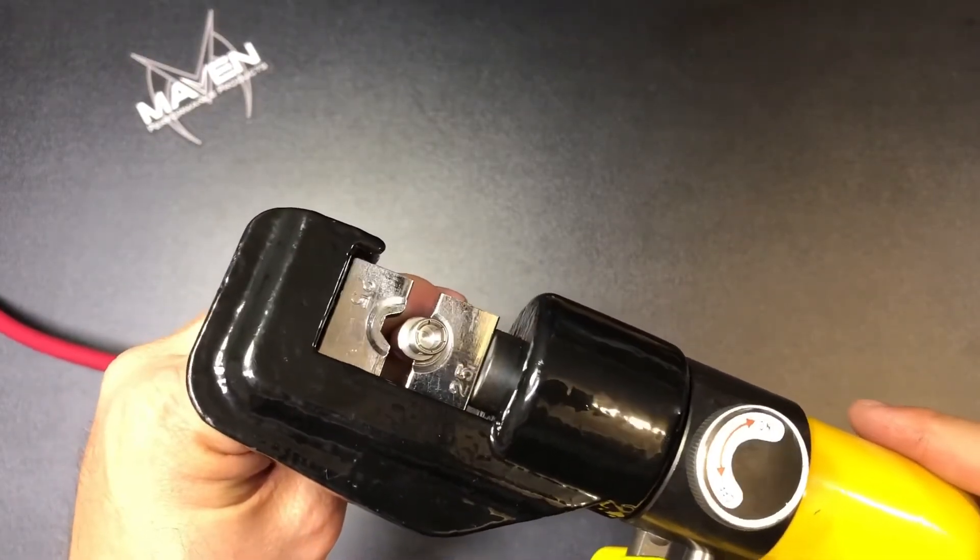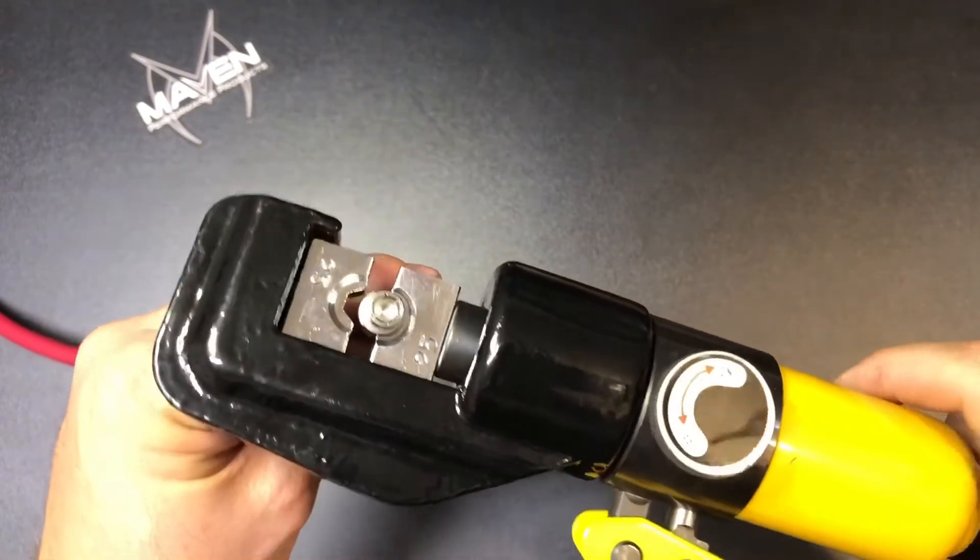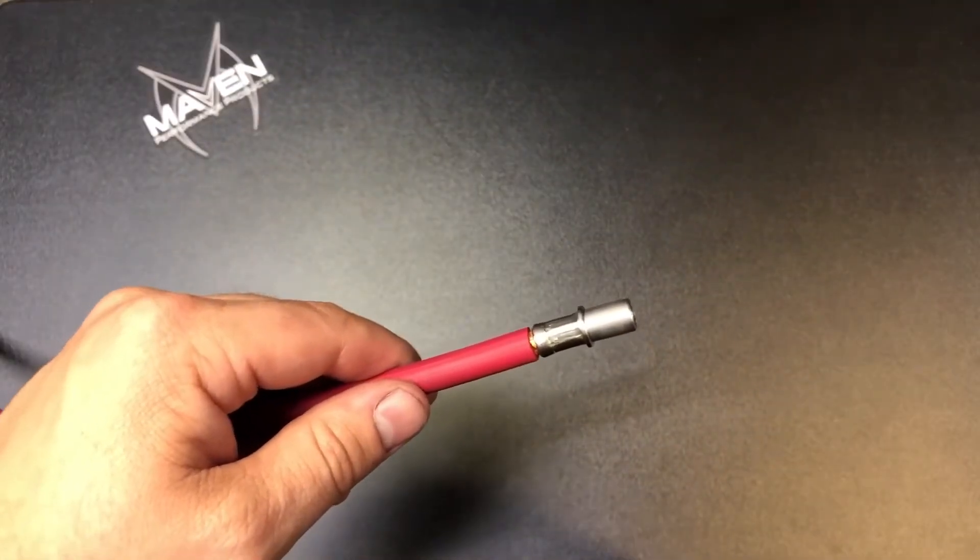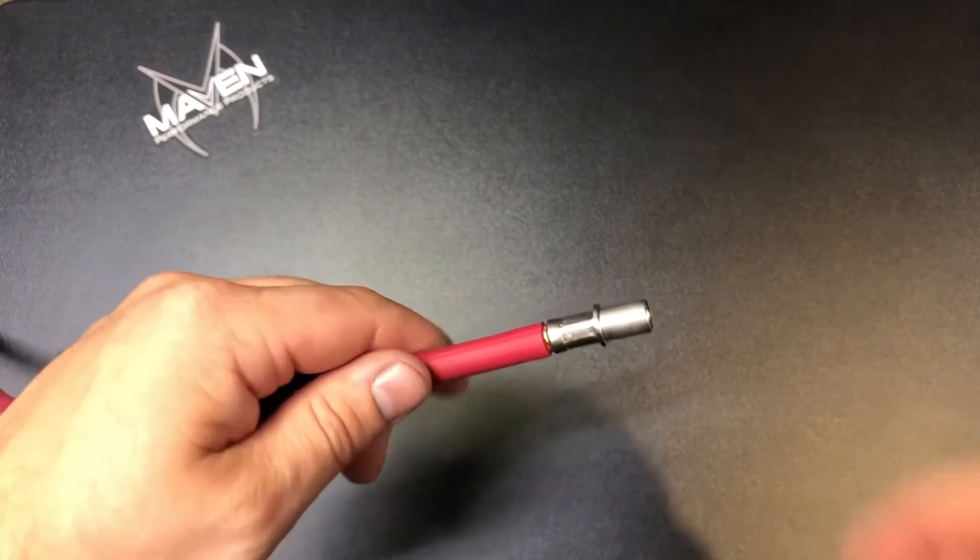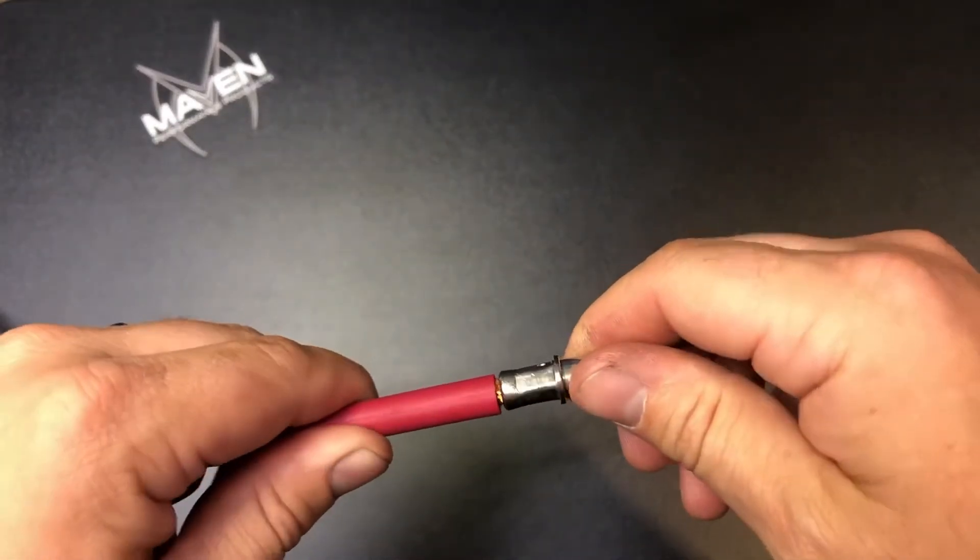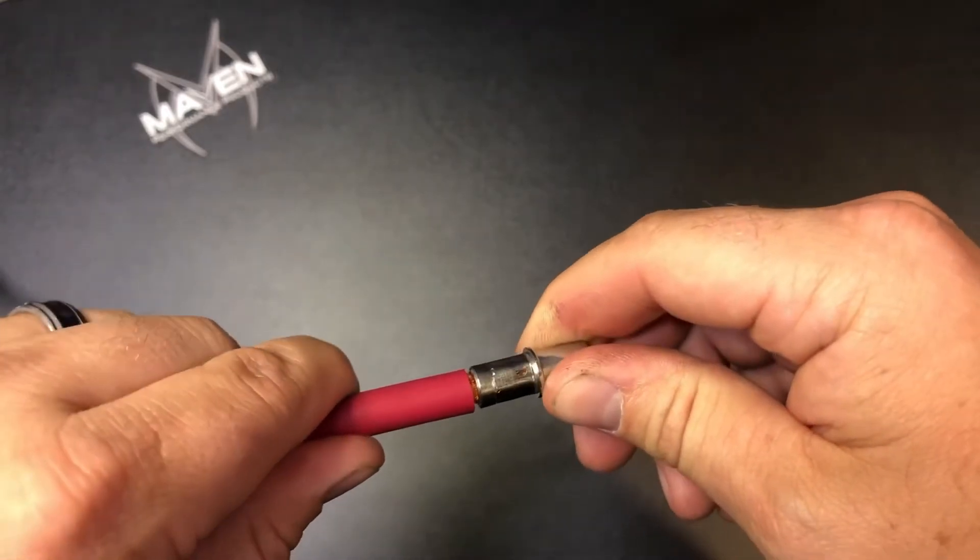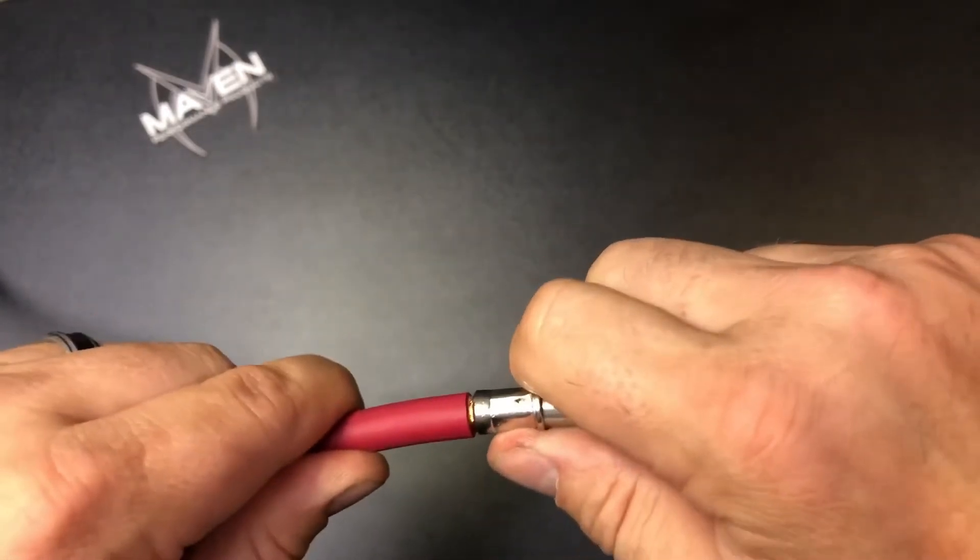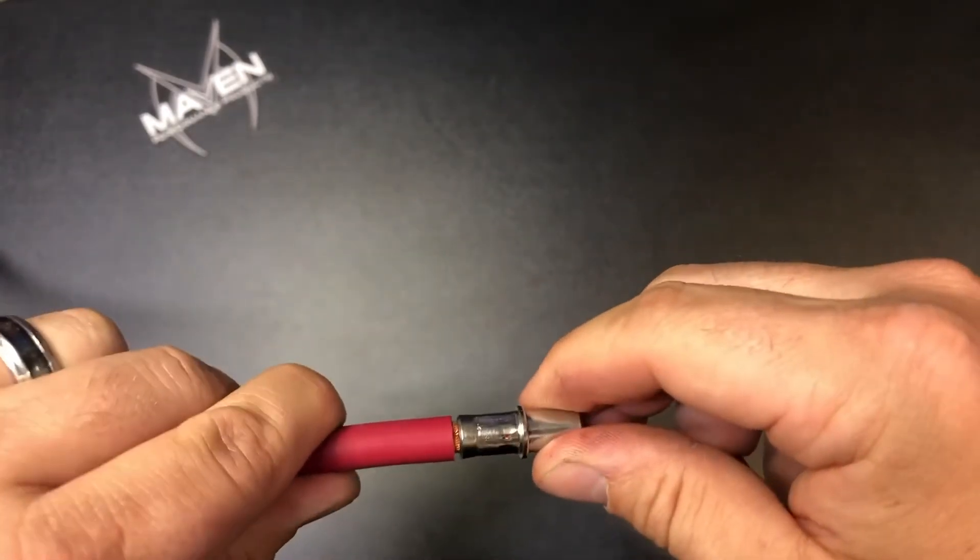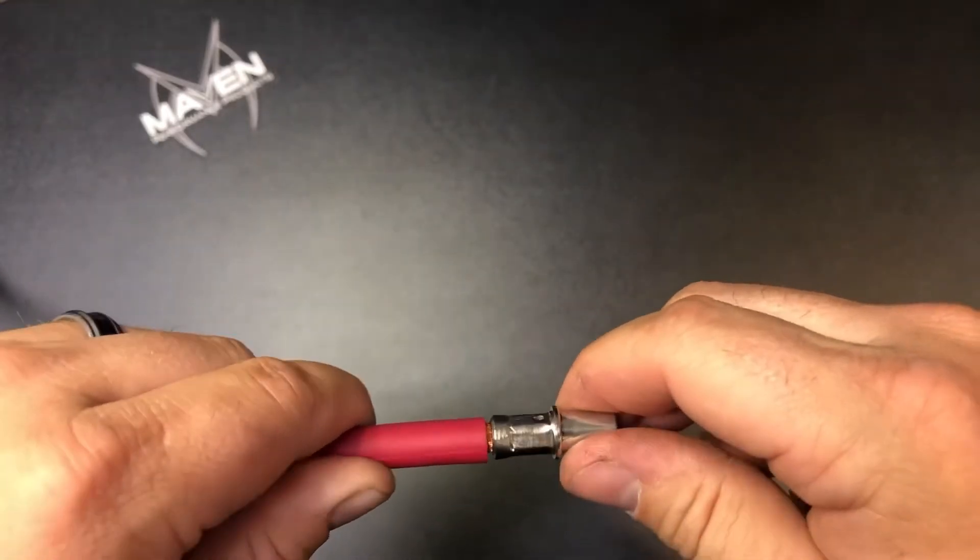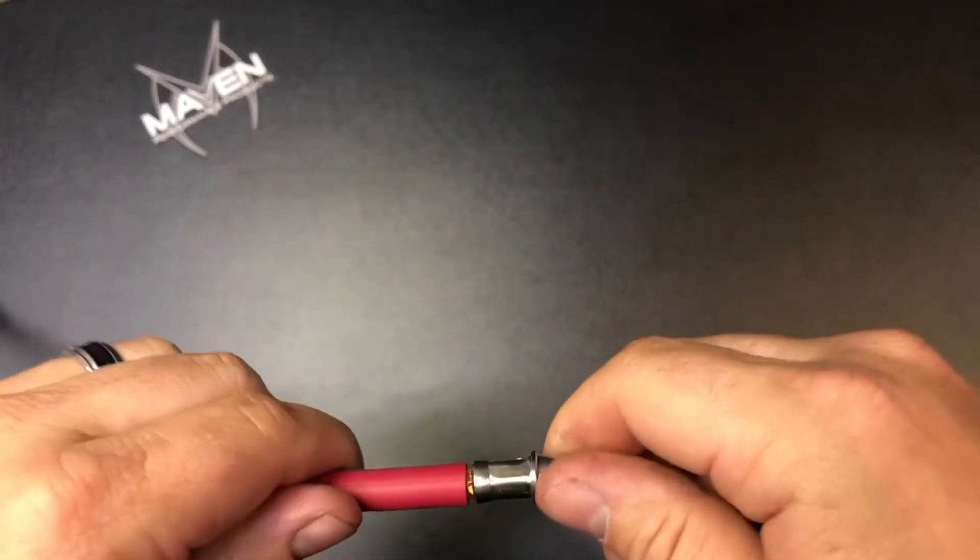After you crimp it, you'll crimp it all the way down till basically the dies bottom out and you can't go anymore. This is what you'll end up with. Of course, it's a hex—you got six sides. You'll see that little inspection hole with all the conductors in there. It's on there. Give it a good tug test to make sure you've got it in there good. So far it's been very successful on a cheap set of crimpers, so give it a go.